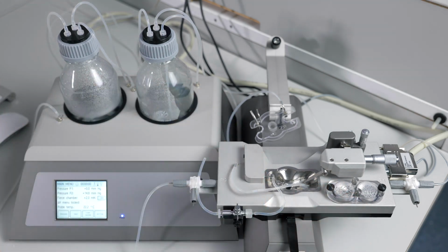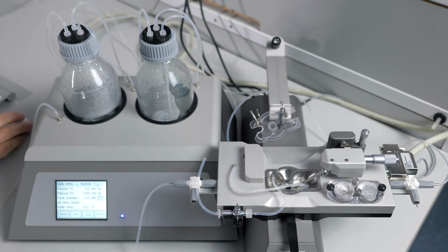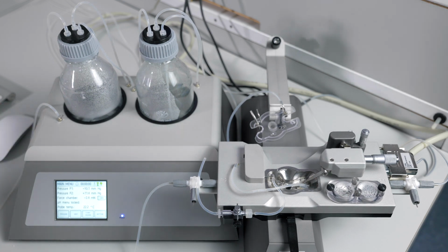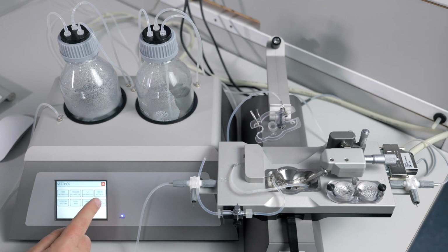We will set P1 to 140 and P2 to 70. We will turn on pressure and flow and let the system push all buffer out into the waste P2 bottle. At this point, you should also go into the settings menu and initiate the cleaning menu. This will ensure that the pulsation wells are also maintained.